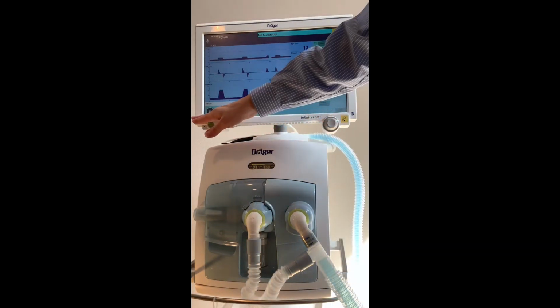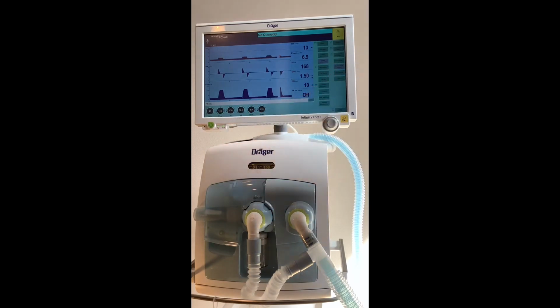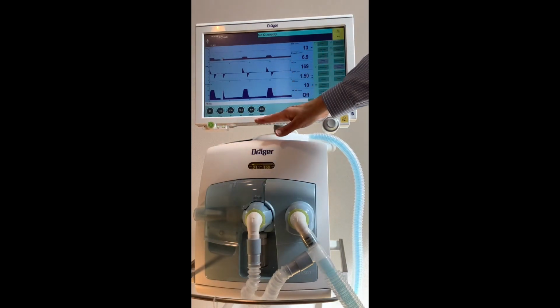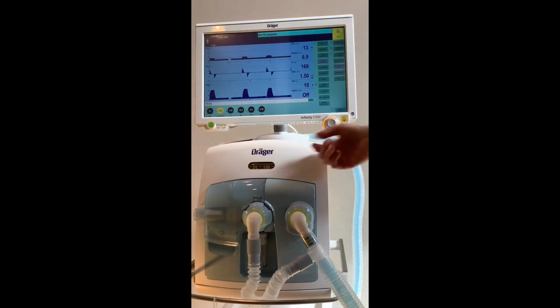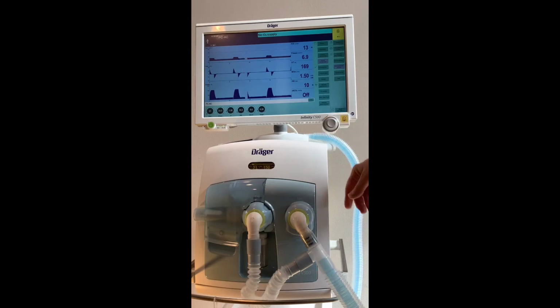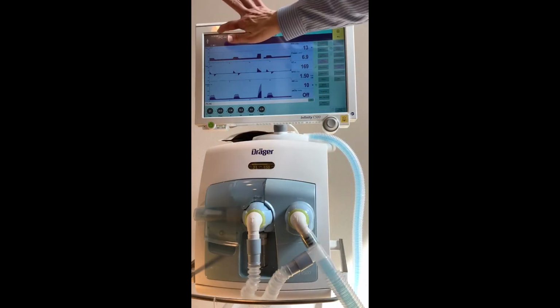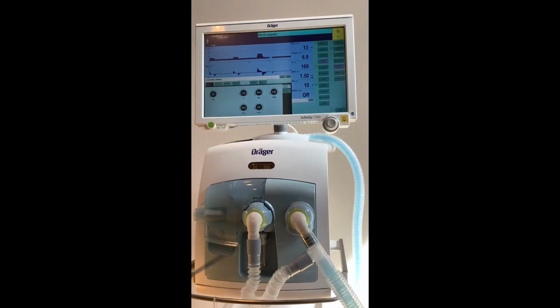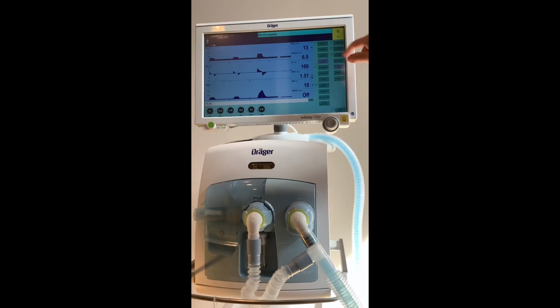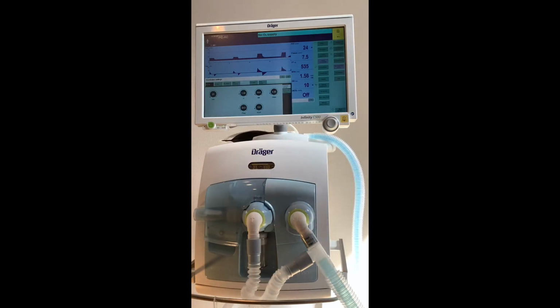In review, your ventilation settings sit in the buttons across the bottom of the control panel. Anything displayed in blue is measured, anything in green is set. To make a change to your parameters, quick set, touch, turn, confirm to make a change. If you need to get to your mode of ventilation or any additional settings, you can touch the mode of ventilation at the top, or you can touch ventilation settings over on the side.